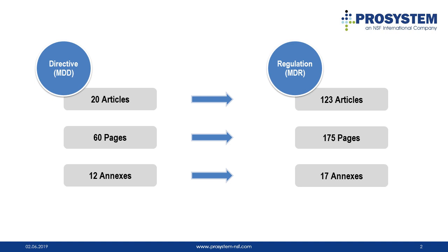Although the new regulation has much more detail and is more stringent, the new regulation follows the principle of the MDD under the new legislative framework, such as conformity assessment, the notified body system, and application of harmonized standards. However, there are also several significant changes introduced. For example, common specifications besides harmonized standards, UDI and EUDAMED, reclassifications, more stringent requirements on clinical evidence and post-market surveillance.